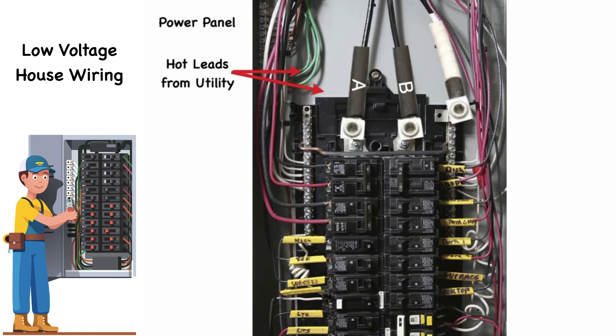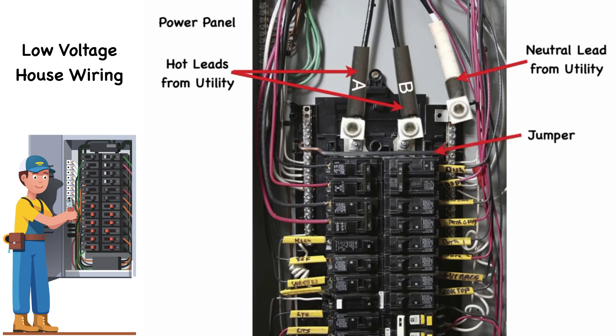This is a more realistic picture of a power panel using breakers. I've indicated where the hot leads and neutral are coming from, ultimately the utility. There are a couple of things to note with this power panel. There is no main breaker, which probably means this is a sub-panel being fed from a main breaker panel. Because the neutral lead from the utility is connected to only one neutral bus bar, on the right-hand side, there is a jumper to connect it to the bus bar on the left-hand side of the panel. This is usually a built-in connection of the power panel.